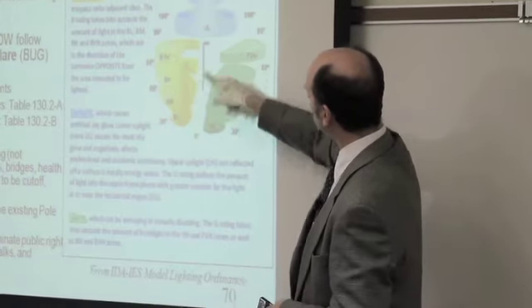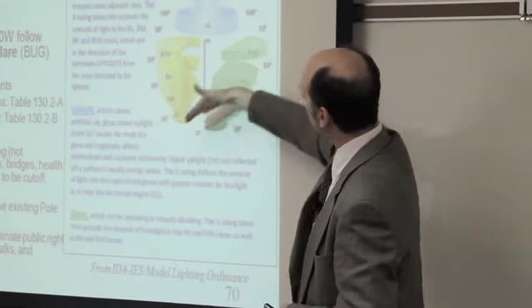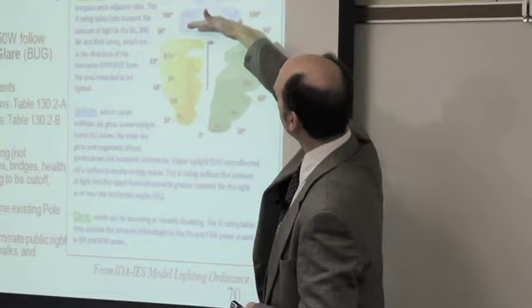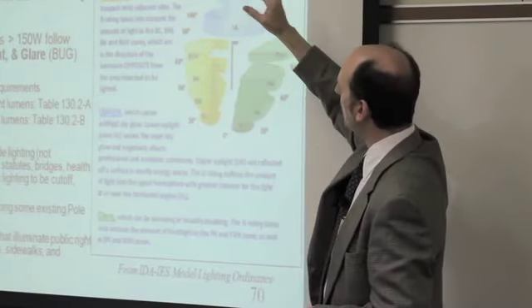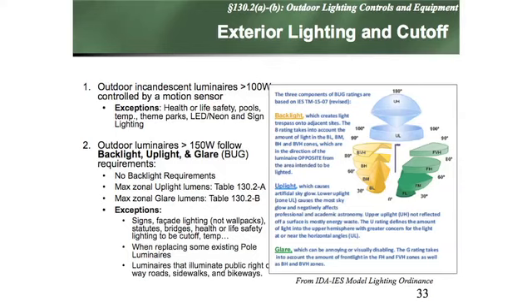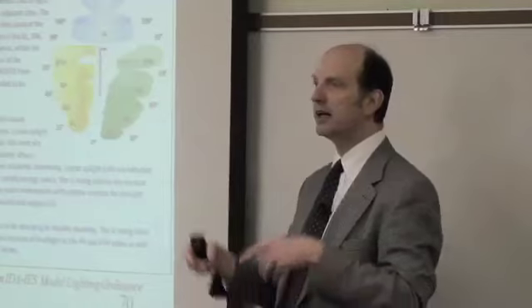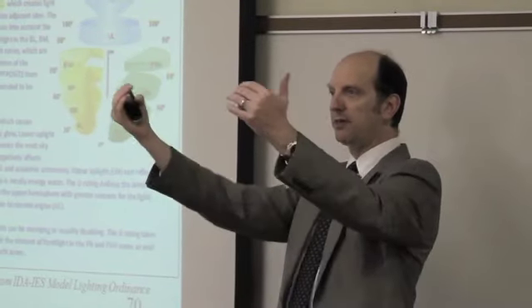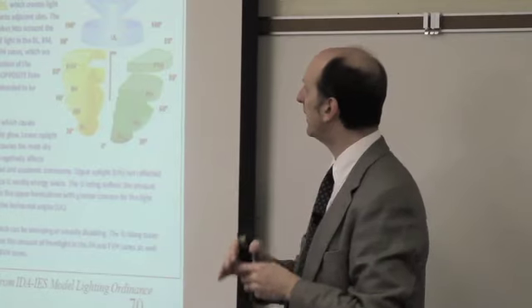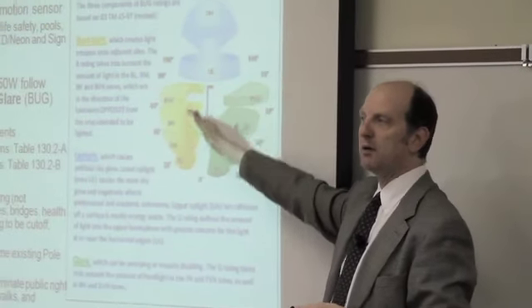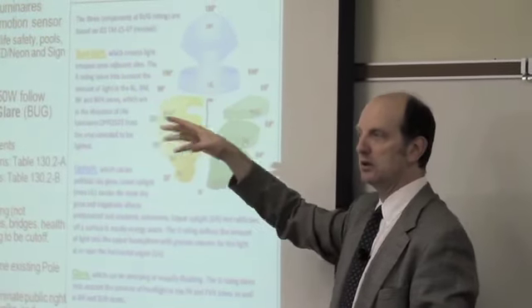So here's a pole. I've got the light that's coming out on the front. I've got the backlight, and I've got uplight. So there is now a whole section of the code that talks about how much light I'm allowed to have on the uplight. And for glare, that's basically the light that doesn't go down. It's the light that goes either 60 to 80 or 80 to 90. You've got a ball field area and somebody's putting lights in. The question is whether or not the houses in the area are going to get any glare. This is what they're going to use to determine whether or not the poles that you use are putting any glare in there.